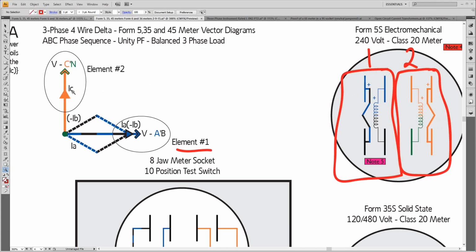said 10 minutes ago or 8 minutes ago, the magnitude of this current is the same magnitude as these two, but when I add these two vectorially, I only get 86% of what the full current would be. And so 86% of this one, 86% of that one would give me the magnitude here. But I have 240 volts across my potential coil. Sitting right in phase, I'm going to get that torque of 86% of those two added together at this 240 volts. And the other element, I'm going to get C to neutral voltage, IC current.